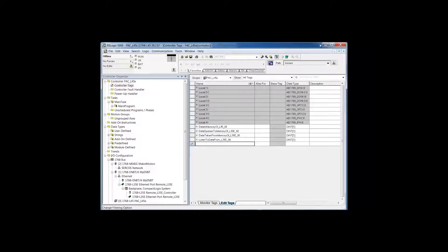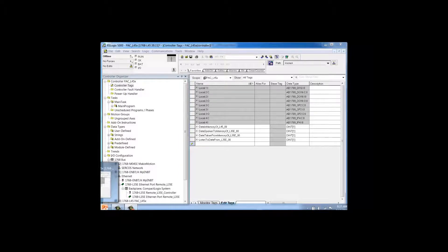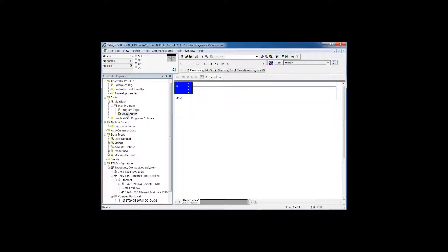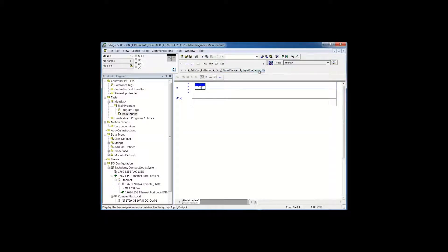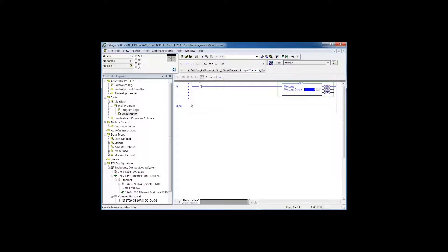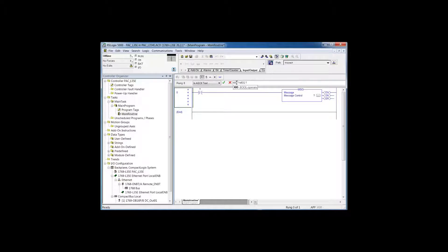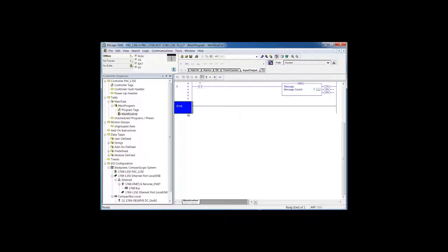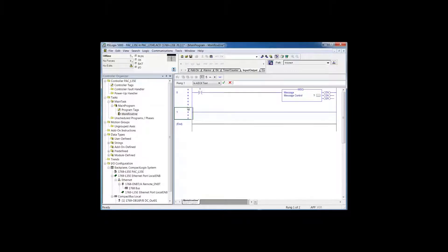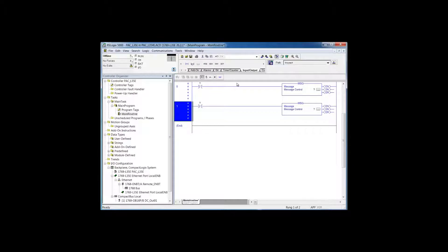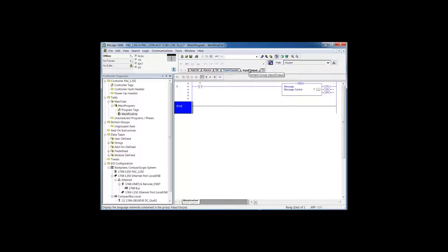Someone has to speak first, so let's go back to the L35E and open up the main routine. There's nothing in it right now. We're going to add a couple of instructions: an XIO (examine if open/false) and a message instruction. I can go to the input/output group and grab message, or I could just double-click and type in XIO space MSG and hit enter. Typically I just create a new rung and type in XIO space MSG, simply because I'm too lazy to drill around on the instruction tabs.